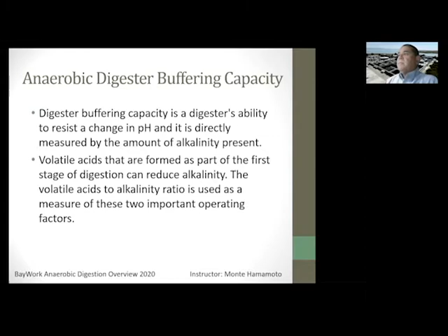In a well-operating digester, the volatile acids, usually expressed as acetic acid, would be in the range of 50 to 500 milligrams per liter, or 500 parts per million. The alkalinity, expressed as calcium carbonate, would be in the range of 2,000 to 3,000. Ours run with volatile acids around 100, and we run between 2,000 and 2,500 on the calcium carbonate alkalinity.